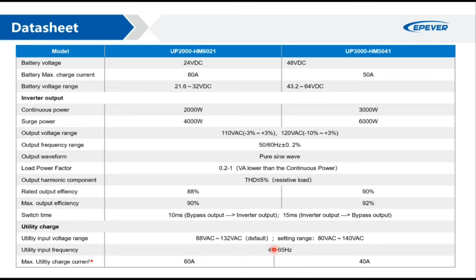And the efficiency is reasonably high, not as efficient as individual modules. So if you look at a single charge controller or a single inverter, you will find higher efficiencies. But there are reasons why the efficiency of a hybrid device is less than the individual components. We will cover it. And as you can see, the utility voltage and frequency range is wide enough to cover all the deviations that might happen in your network. The PV charging characteristics are also demonstrated here.